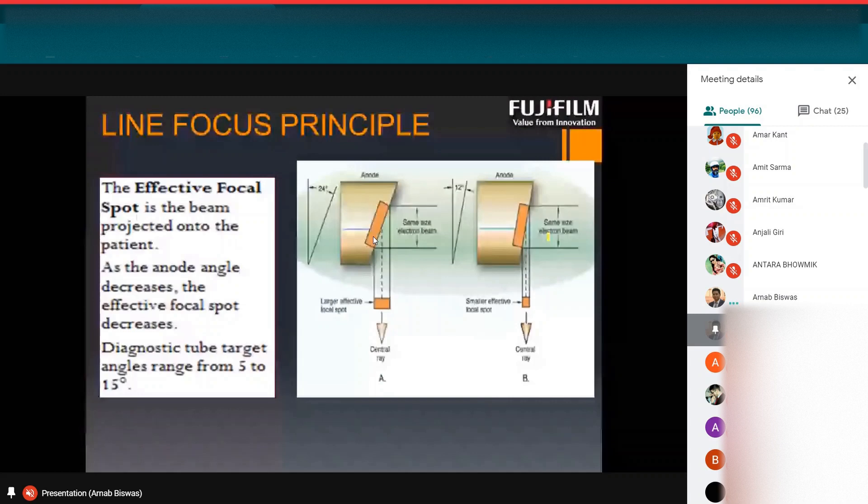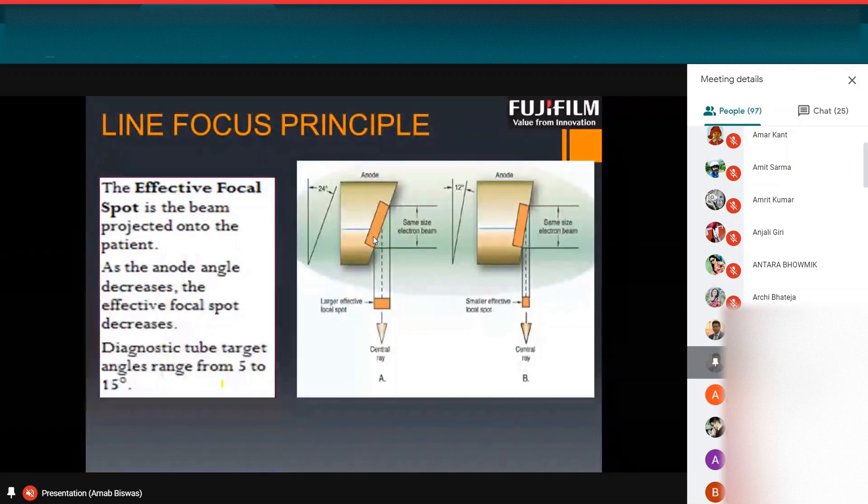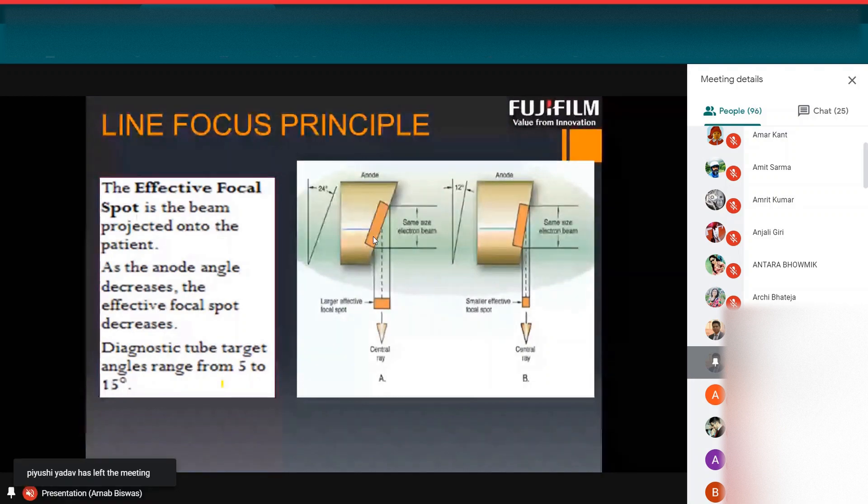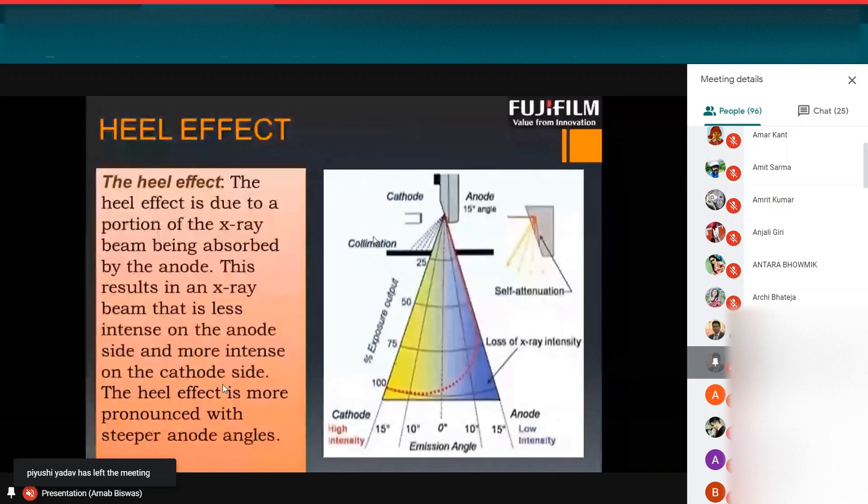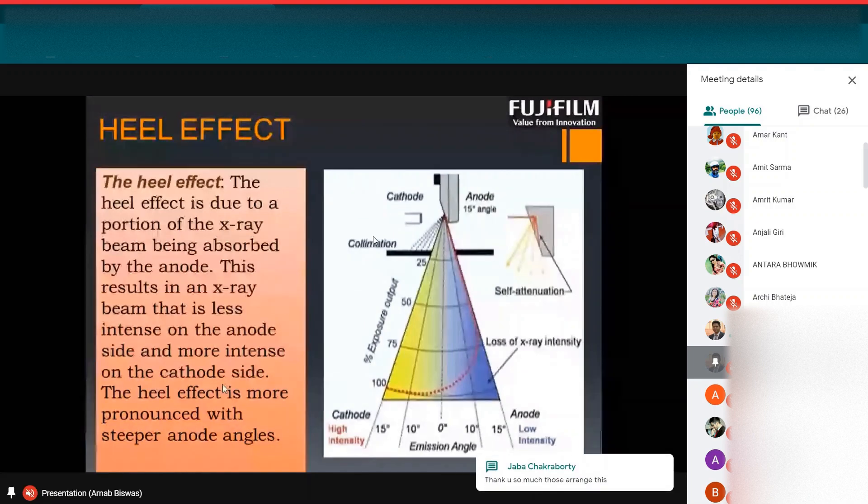Because the anode angle is higher, the focal spot is higher. This is directly proportional, that if you increase the anode angle, the effective focus spot will increase. Diagnostic tube target angles range from 5 to 15 degree. Due to anode angle, we use 15 degree anode angle. And when the electrons collide to the anode, it travels through an angle. So here, heel effect is causing this.